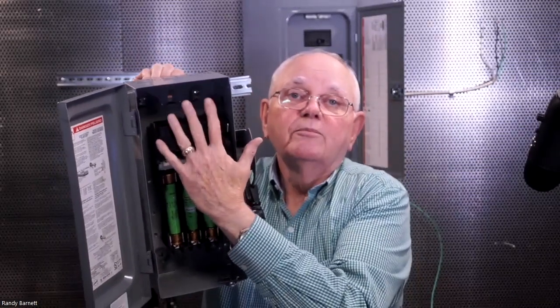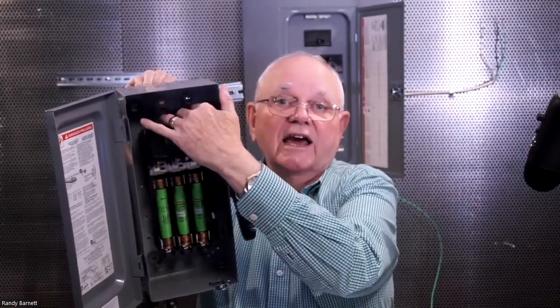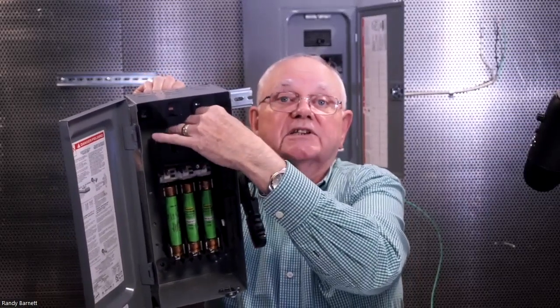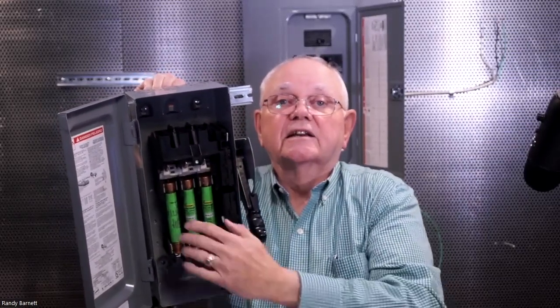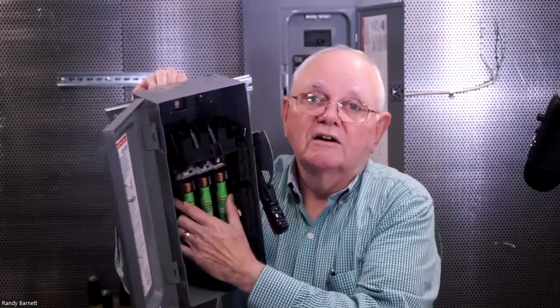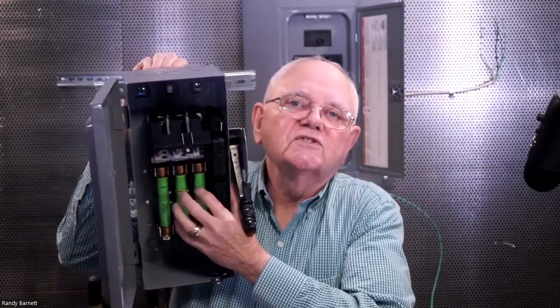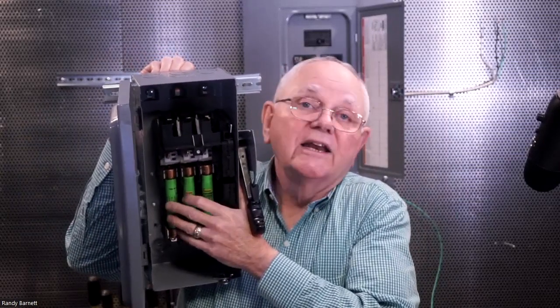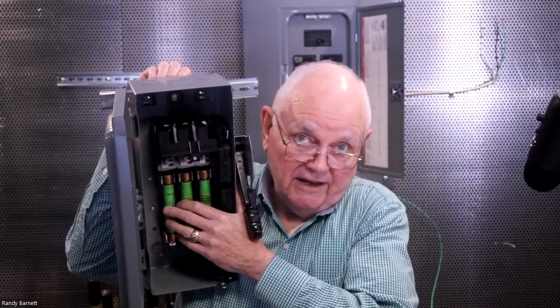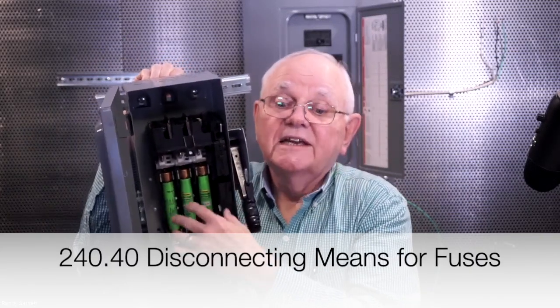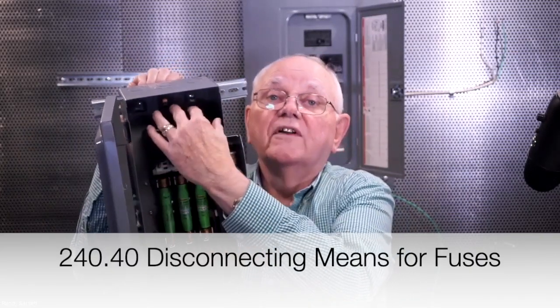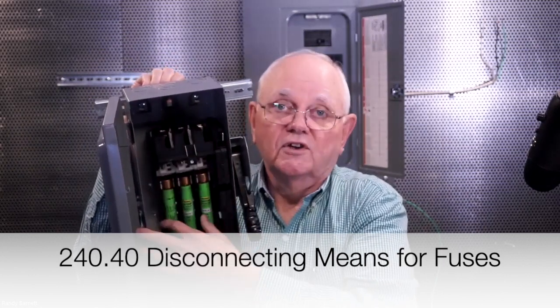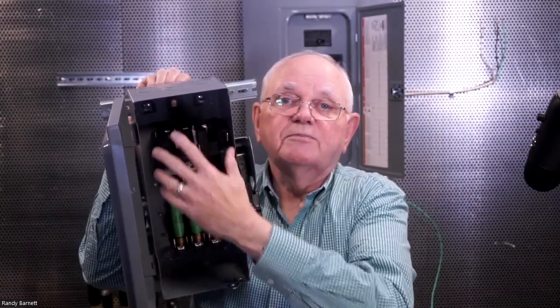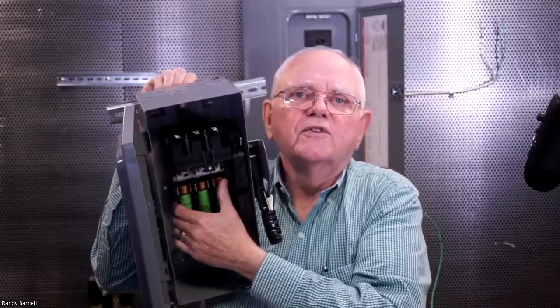Even though I pulled the blades out, I still have 208 or 480, whatever it is, coming into the top of this disconnect. So even though my fuses are de-energized, Article 240 also tells you that for cartridge type fuses and any fuses that operate at greater than 150 volts to ground, I have to have a disconnect switch on the line side of the fuses so that I can shut the power off to the fuses and remove the fuses.